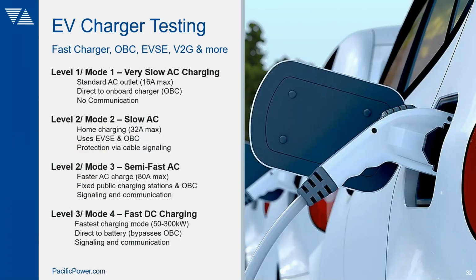EV chargers are a common EUT these days because of the electrification of transportation. There are several levels of these. Of course, there are 3 levels and 4 modes. Different levels of charging give you higher charging speeds, operating at higher voltages and currents. So to test these, you have to size your grid simulator accordingly. Mode 3 is for public charging stations, and they can be higher power.